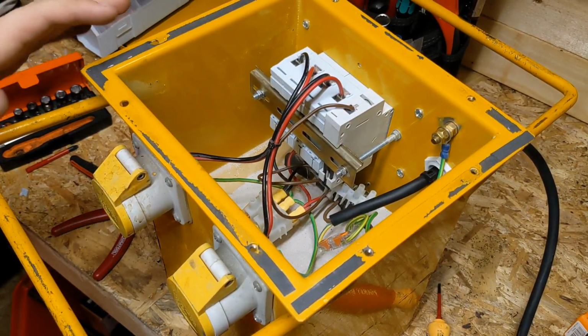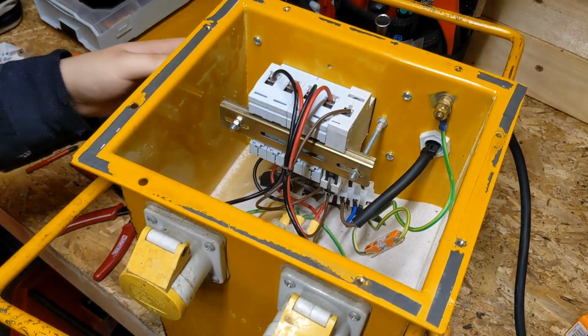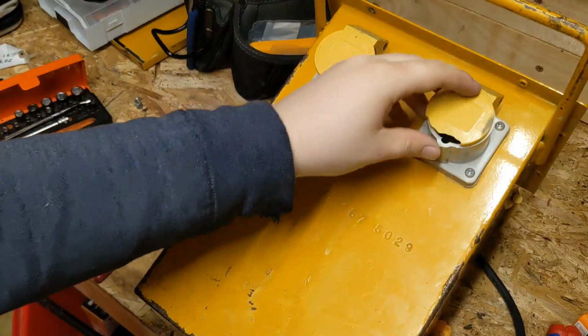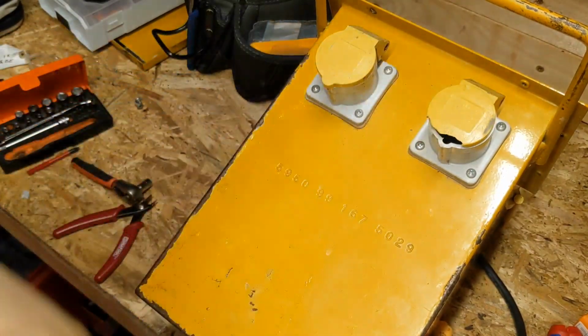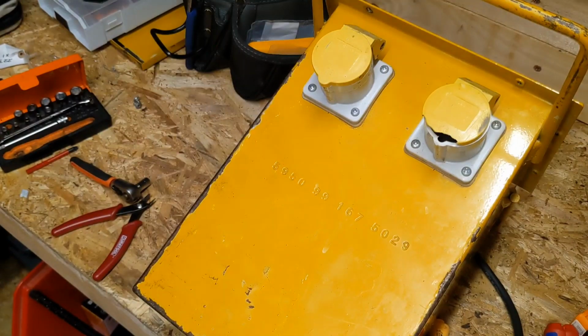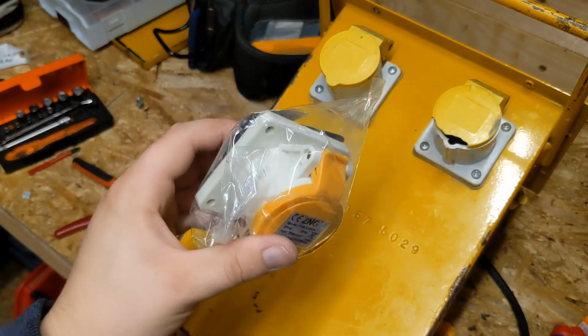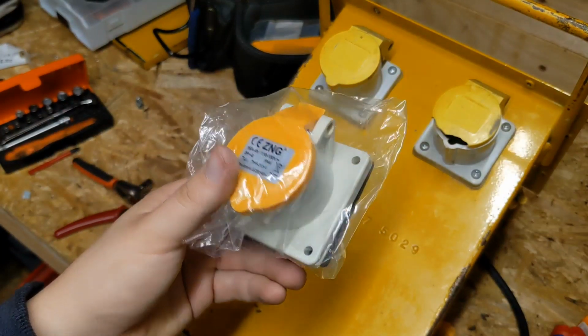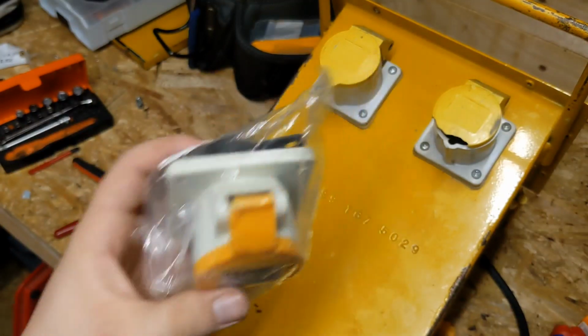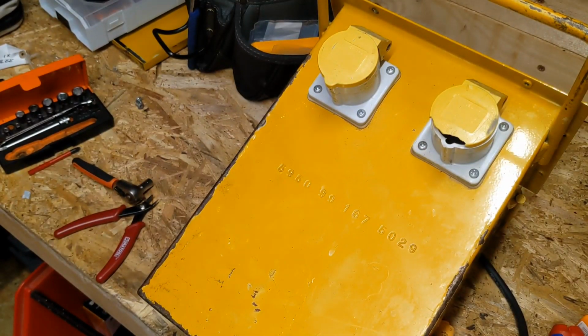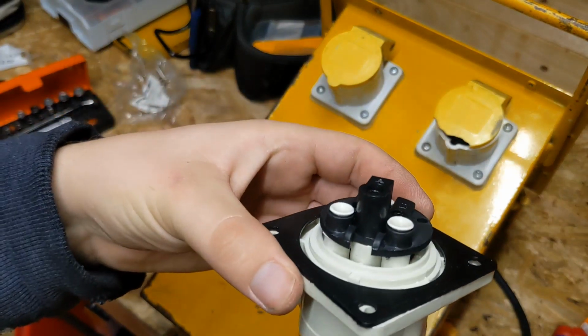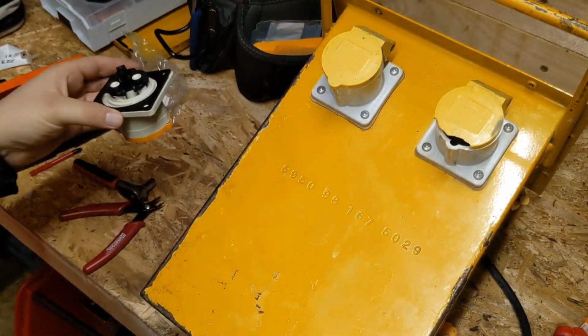Done like so. Now we'll do the socket on the front, because the shutter's broken and a bit wobbly, so we'll put a new one on. If you do a lot of electrical maintenance like me, you carry these panel mount 16 amp, 32 amp sockets all the time. So we'll grab one of those - make sure you always get one with a rubber gasket, as sometimes they come through with no gasket on.